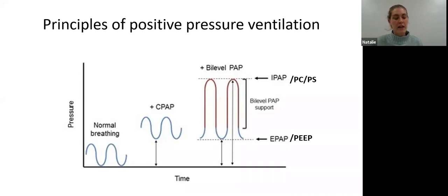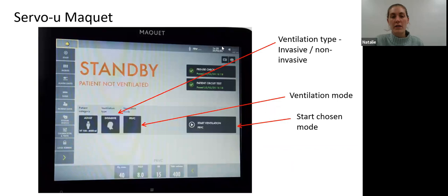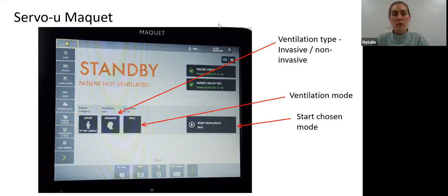Now linking ventilation in general to what we might see in practice, we're going to focus mainly on the Maquet - the ventilator we see on ICU. This is the Servo U Maquet, which most people working on ICU out of hours will be familiar with. This is the standby page. The first arrow points to the type of ventilation - we can have invasive or non-invasive. The second arrow points to the ventilation mode which we can go in and change. The button on the right starts whichever ventilation type and mode you've set.